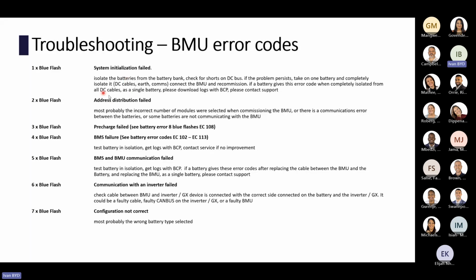System initialization failure means something's not working properly, and that's a sort of a catch-all. And BMS failure is almost always issues within the battery that need to get sent to the workshop, but you do have to look at the error code on the battery to double check. BMS and BMU communication failure is a communication issue between the BMS and BMU, and almost always this is a common one.